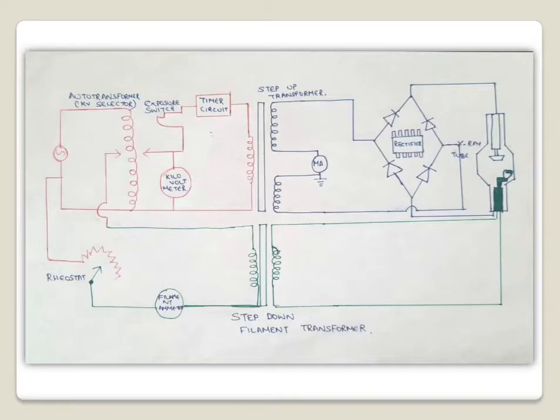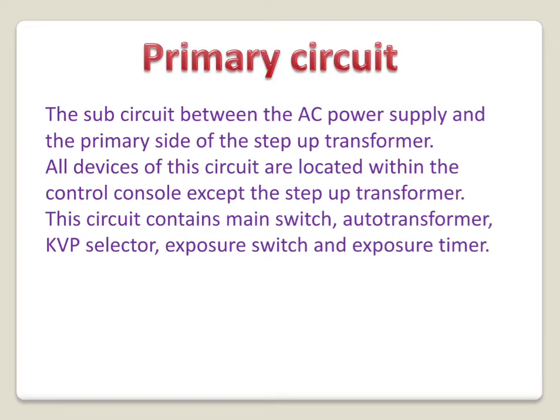In this image you can see the x-ray circuit. The part shown in red color is the primary circuit, the part shown in blue color is the secondary circuit, and the part shown in green color is the filament circuit. The primary circuit starts from the source of alternating current up to the primary coil of the step-up transformer.